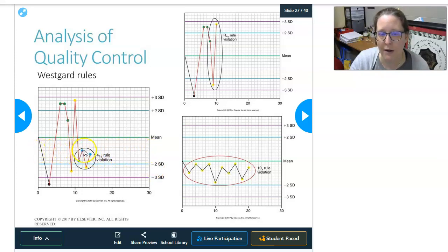And so if you have these points starting to congregate north or south of that 1 standard deviation line, then you're looking at a possible shift or a possible trend, and you could be getting into trouble. So it's like a warning to look at it and see what's going on. So that's a 4 1s, 4 points outside of 1 standard deviation.